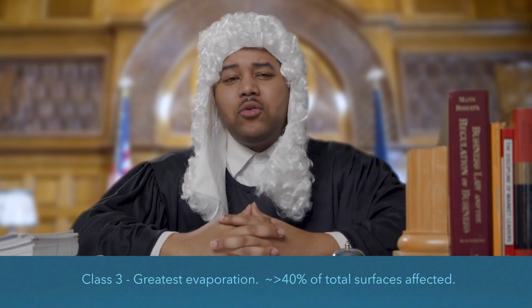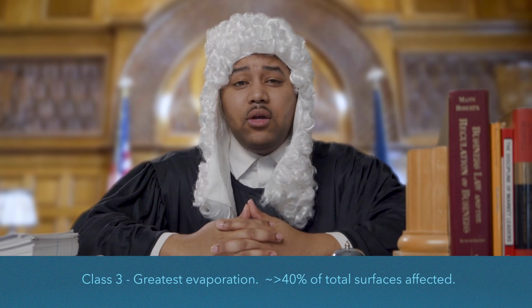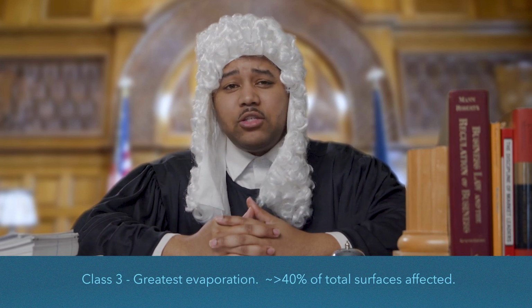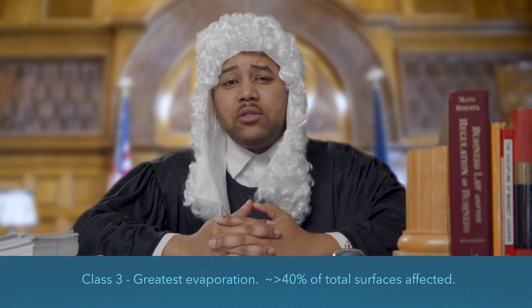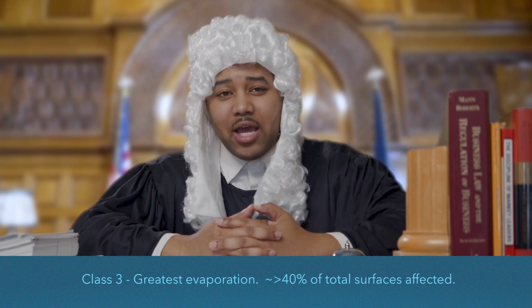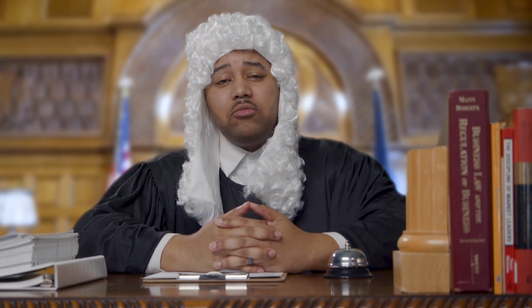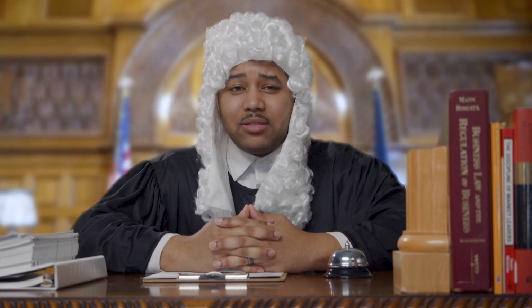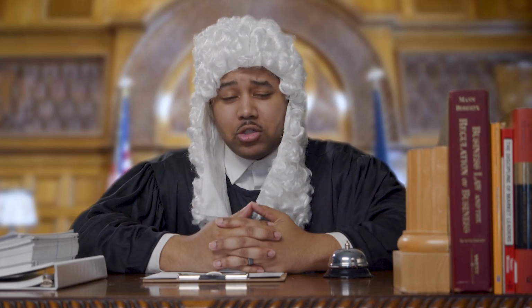Next you have Class 3. This is the greatest amount of water absorption and evaporation load, where you have water intrusion where wet, porous materials such as carpet, gypsum board, fiberfill insulation, concrete masonry unit, they represent more than 40% of the combined floor, wall, and ceiling surface area in the space, and where materials described as low evaporation materials such as plaster, wood, concrete, masonry, or low evaporation materials, once again, multi-layer wallboard, multi-layer subfloors, gym floors, other complex assemblies, have absorbed minimal moisture.